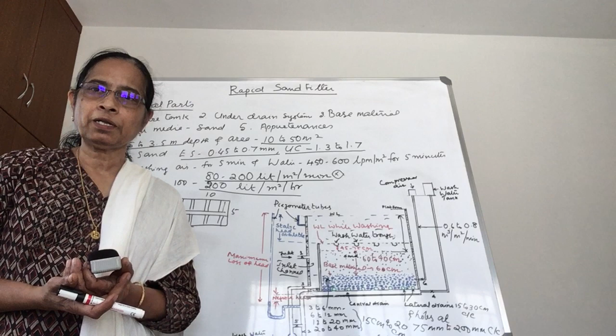In the slow sand filter, biological action is the foremost function taking place. That is the formation of the schmutzdecke, and the further filtration through the sand media is basically through the schmutzdecke, that biological media layer. In the slow sand filter, we allow the schmutzdecke to remain for a longer period, and we clean the sand media only once in 3 months or once in 6 months. That means the schmutzdecke sustains in the filter box for a longer period, whereas in the rapid sand filter, it is not like that.